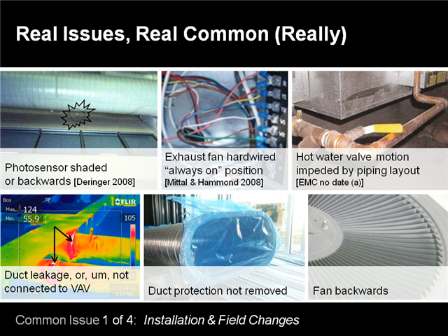And then we had problems where we've seen that the protection, which is nice because the contractor will protect the ductwork during construction to stop it from becoming dirty when startup comes, and then they forget to take that plastic off. And then they operate the system, and we're not getting any air into the space. In this case, we pulled the floor up because it was an underfloor system and found that the duct protection was still in place. So the dampers are running, and the contractor says, oh yeah, that system's working, watch the damper operate. Well, it wasn't operating, and the system was balanced, by the way, already.